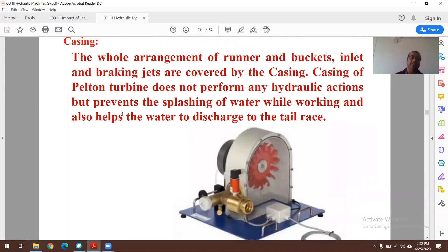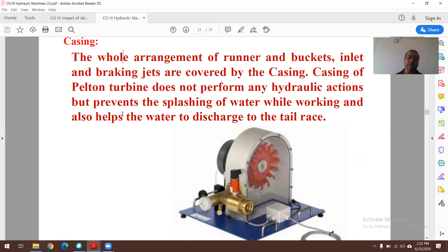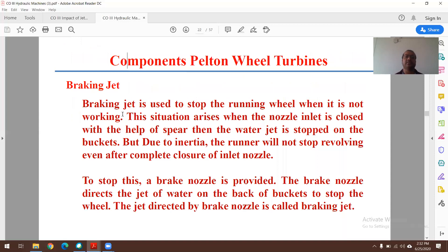The casing covers the whole arrangement of runner and buckets, including inlet and braking jets. The casing of a Pelton turbine does not perform any hydraulic action, but it prevents the splashing of water during operation and allows water to discharge smoothly to the tailrace. Even if the casing is removed, the turbine can still run — unlike in a reaction turbine, where casing plays a hydraulic role.